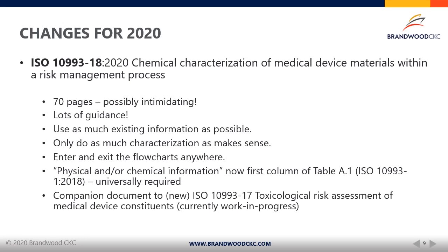There are, in this revision, some very good flowcharts to guide processes and activities in characterizing the device. And these flowcharts can be entered and indeed exited anywhere. So you don't have to start and work your way through masses of processes on the flowchart and then finally come out at the very end of the chart. You can enter and exit as is most appropriate, and this very much goes with the previous 2 points on the slide, to only use existing data if it's possible and to only do the characterization that is sensible. And the flowcharts and this permission to enter and exit where necessary is entirely consistent.